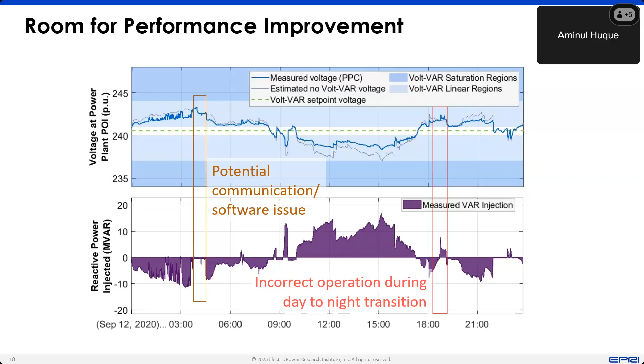The key takeaway: if the right technology is used and it's in the scope of the project, the solar PV inverter can provide reactive power support at nighttime, but there is a cost — in terms of active power demand to keep the plant operational, whether it comes from a source inside the plant like a UPS or small batteries, or from the grid. That has to be factored in.